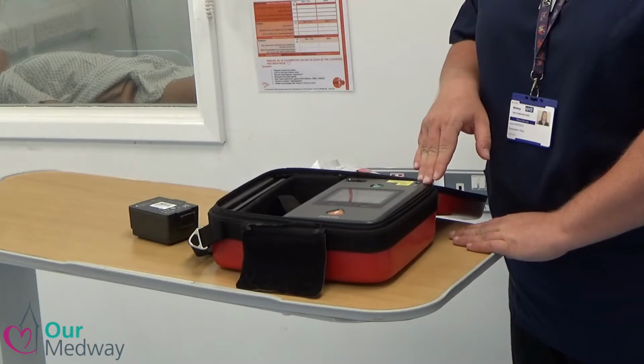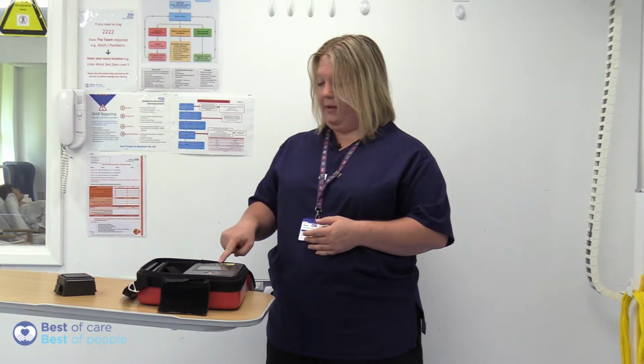When we change a battery, or if we have any concerns about the defibrillator, then it's good practice to do a user test. Like I say, the defibs will self-test every 24 hours, and as long as we have a flashing green light at the top there, as you can see, this defib is ready for use. But if you've changed a battery, or if you have doubts, then do a user test. This is really simple to do.